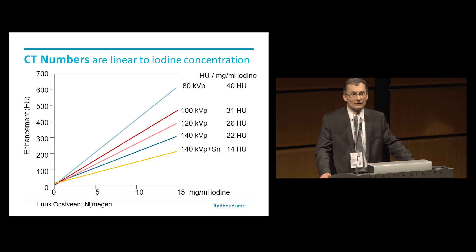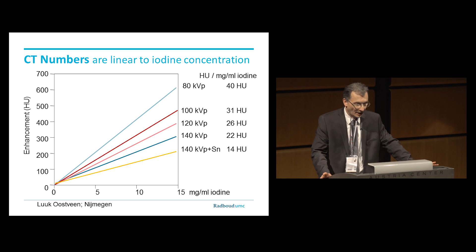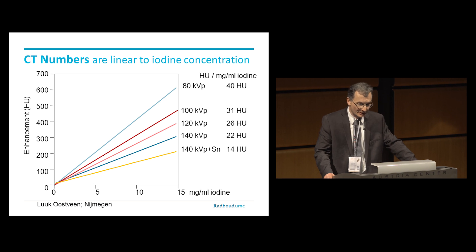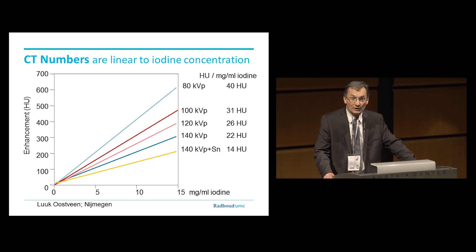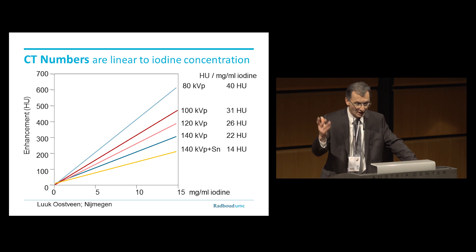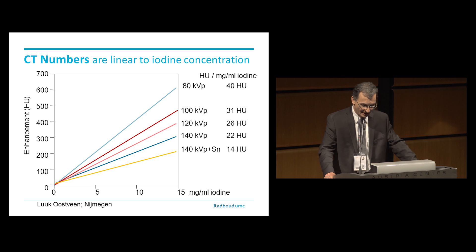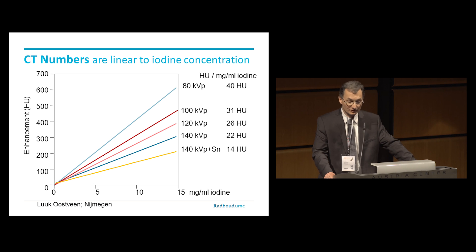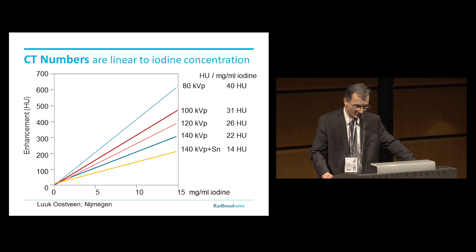The iodine concentration is directly proportional to the CT numbers, and the lower KVP obviously gives you more attenuation per milligram iodine. For example, at 80 KVP, that's about 40 Hounsfield units per milligram per milliliter concentration. And at 140 KVP, that is about 22 Hounsfield units. If you take an additional tin filter, this can go down as little as 14 Hounsfield units.